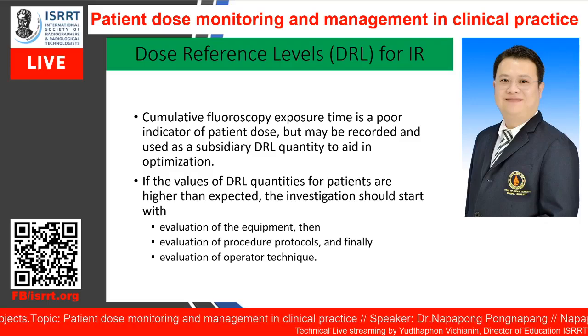But the funny thing is, when I work with a lot of hospitals, in a lot of places the dose metric is there, but it doesn't show on the monitor because the service engineer did not enable this option. So when we first want to monitor, we have to check if your modality has the option or not. If it has the option, you have to show it.